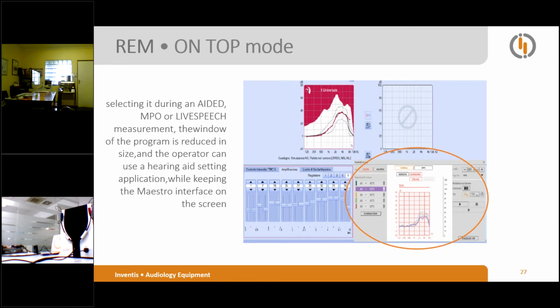For instance, the picture shows an example of how to use the on-top option. The operator who is performing an REM examination can adjust the gains of the hearing aid from the software provided by the hearing aid company, and assess at once if the measurement acquired, in the example 80 dB SPL REAG, moves close or away from the corresponding target curve. So it is a very important feature because you can use two different software at the same time. You can use the hearing aid software in order to adjust the gain. And at the same time, you can use Maestro and check if the curves acquired are close or not to the target curve provided by the fitting rule.